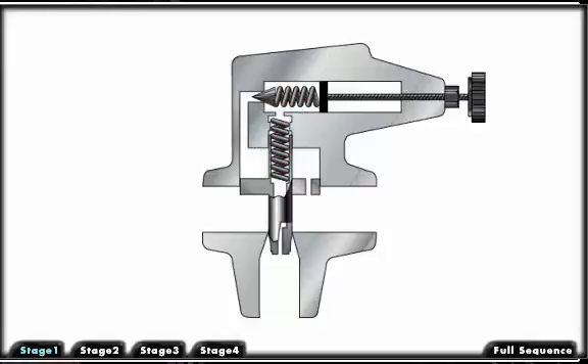The second stage is large enough to handle the maximum flow rating of the valve. The first stage is a small direct-acting relief valve, usually mounted as a crosshead on the main valve body, and includes a poppet, spring, and adjustable knob.